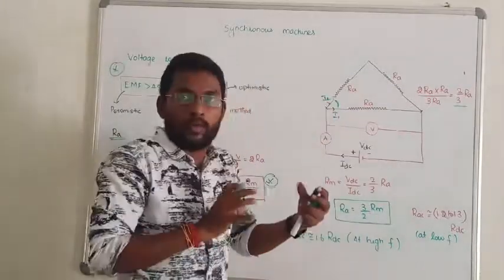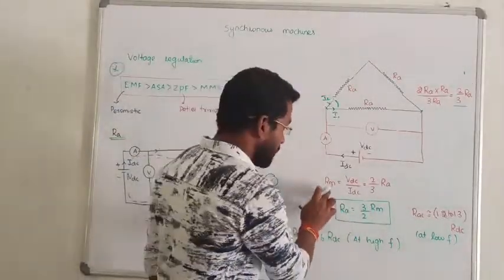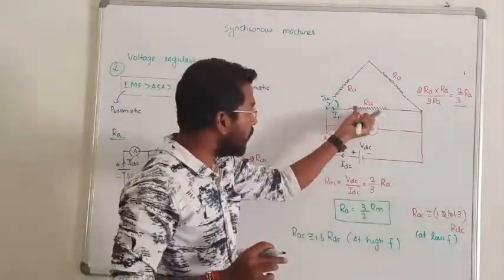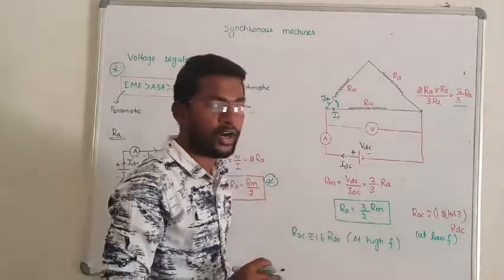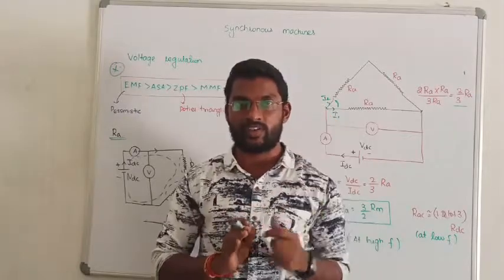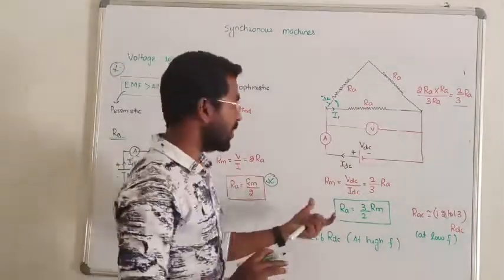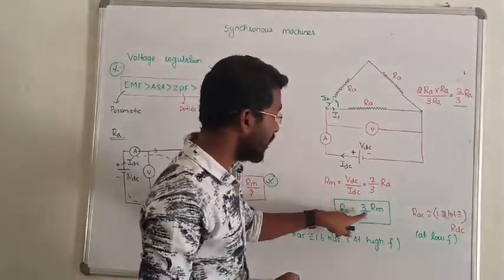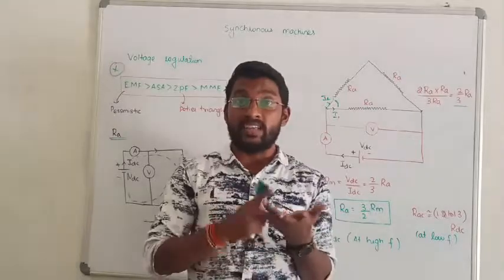So what is the conclusion? For a star-connected machine, the measured line-to-line resistance is 2 × R_A, so R_A equals the measured value divided by 2. For a delta-connected machine, the measured value is 2/3 × R_A, so you divide by 2/3 — or multiply by 3/2 — to get the actual per-phase armature resistance.